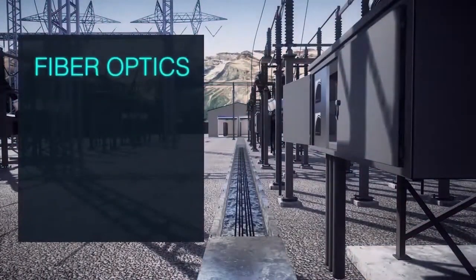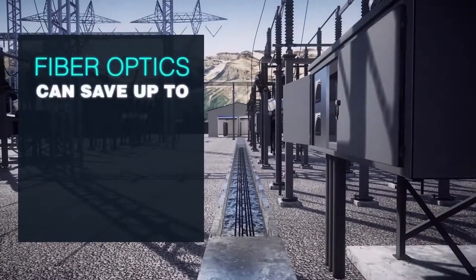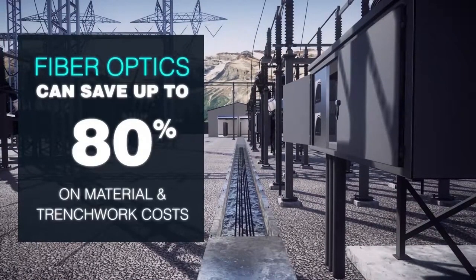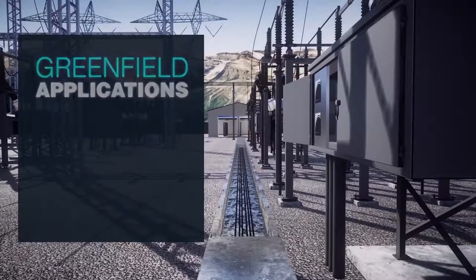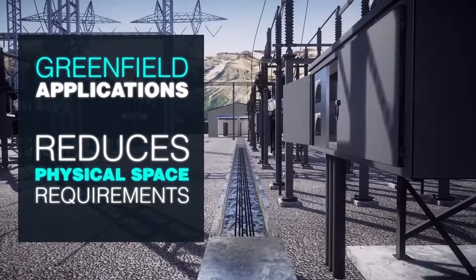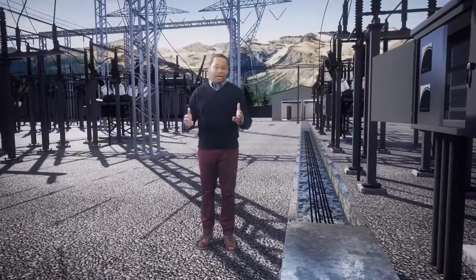When copper is replaced with fiber optics, you can save up to 80% on material and trench work cost. And in greenfield applications, the physical switch yard space requirements are significantly less, which is another cost advantage. This is the start of our process bus, a secure digital communications pathway that distributes data more efficiently when compared to conventional analog architectures. It's time to see where these wires go.